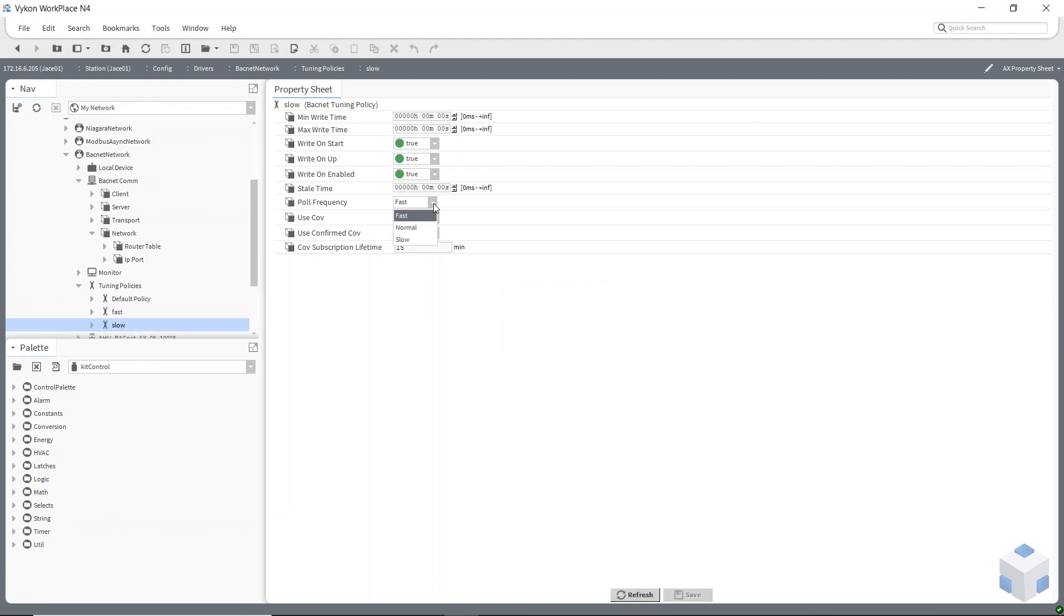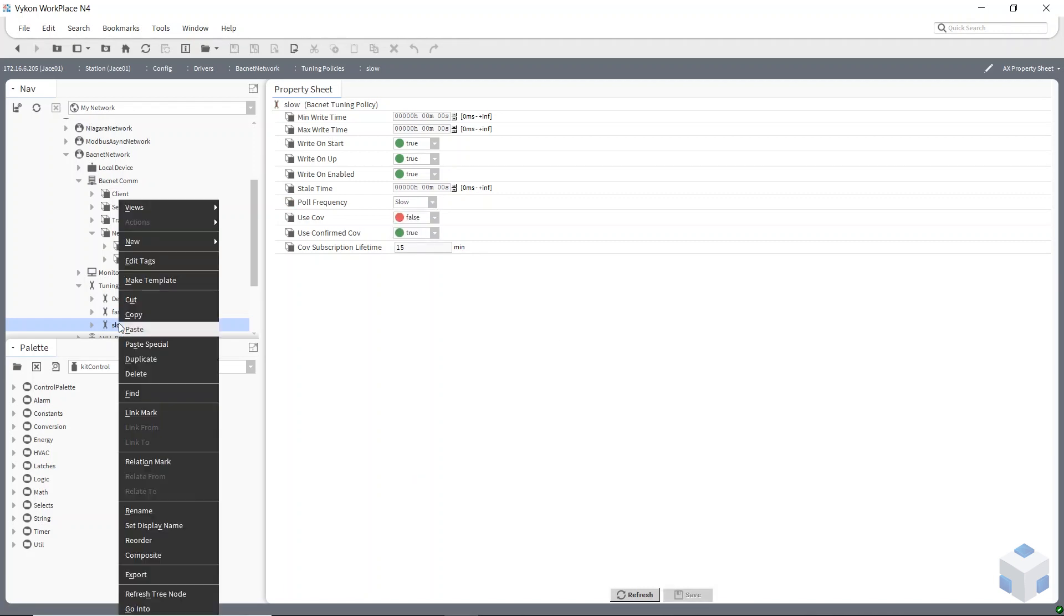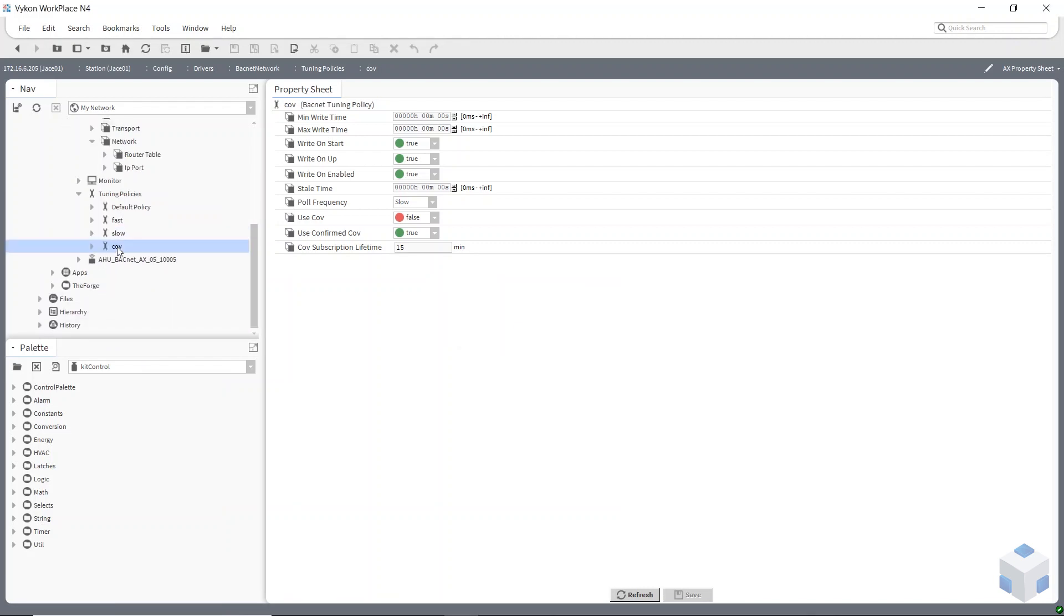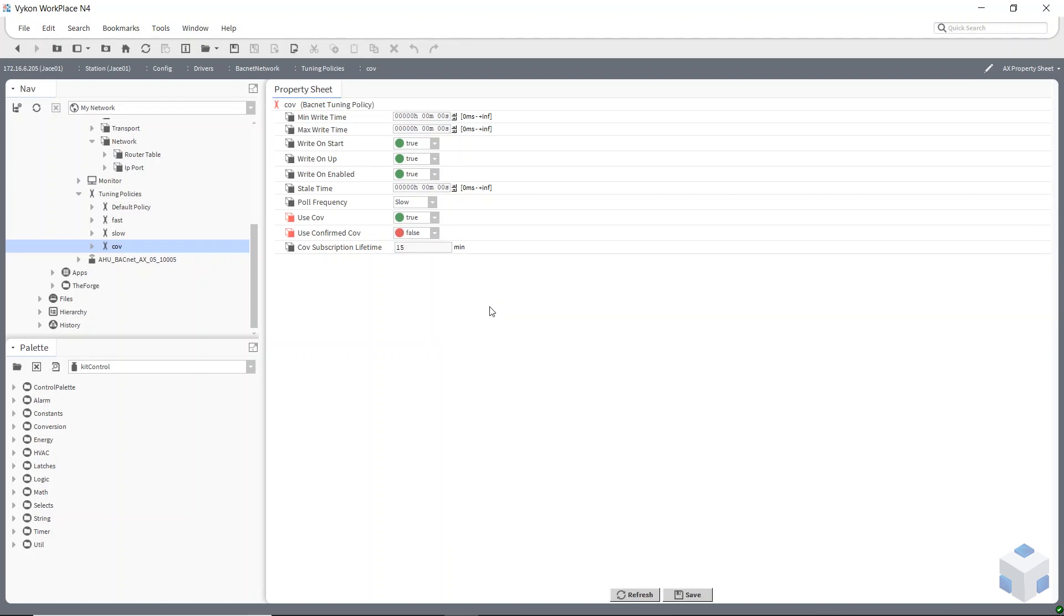Edit that one and also a good idea to have a COV change of value. So if I duplicate it again, I can edit that one now. What I can do now is change where it says use COV, I can change that to true. Once you've selected that it will just ignore the poll frequency and just use change of value. And you've also got use confirmed COV. You don't need to use that if you can get away without using that then I would suggest you don't use that because it just uses a bit more comms.